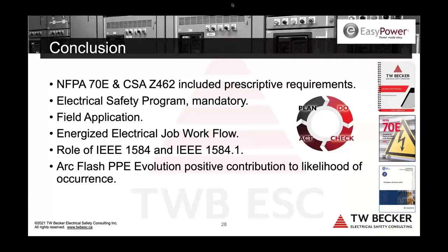So again, 1584 and 1584.1, very important standards, 208 volt three-phase to 15 kV, other formulas for greater than 15 kV. And 1584.1, I cannot emphasize enough, it's just not known. If you don't have it, buy it. You're going to go, this is amazing, because it backs up your study. It gives you the proof to your client that you're following 1584, but 1584 gives you the formulas.